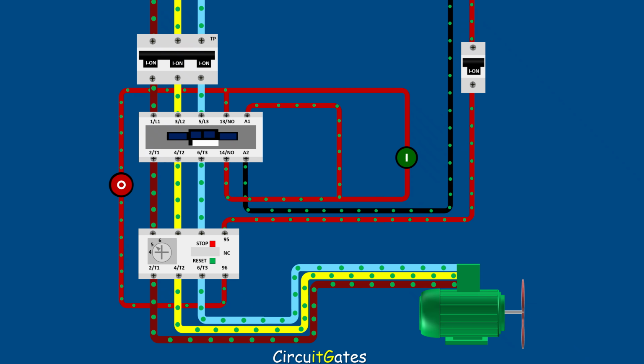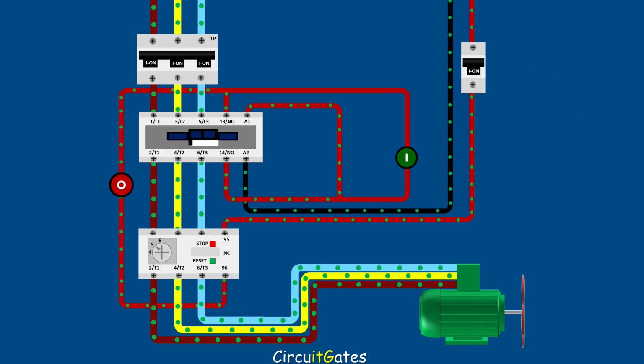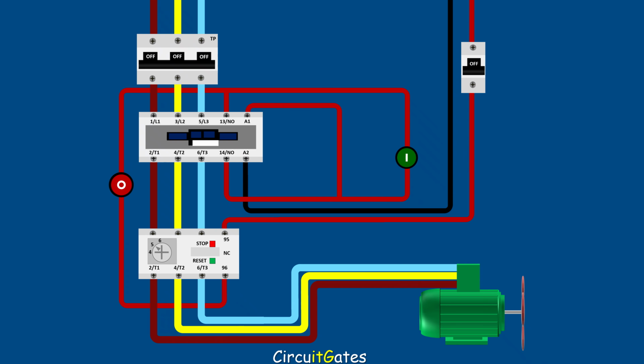Circuit breakers are devices that are manually operated to switch off the circuit for maintenance, or they automatically trip, cutting off the power in the event of an overcurrent condition, usually due to short circuits. In the event of some small overcurrent due to overload, circuit breakers do not trip, since circuit breakers for electric motors are only equipped with a mechanism for short circuits, not for overload. Therefore, there is a need for an overload relay.